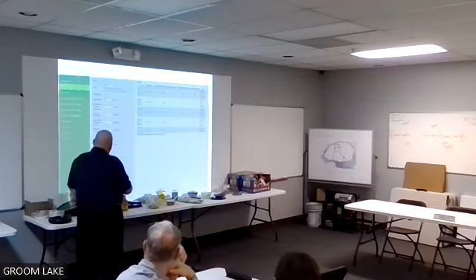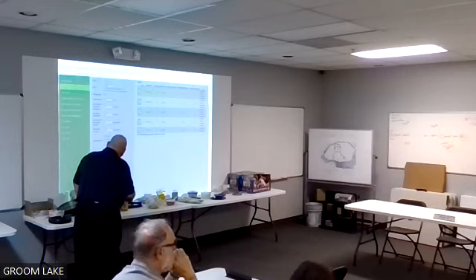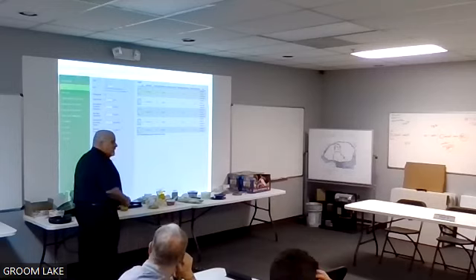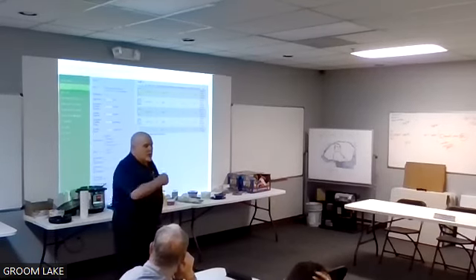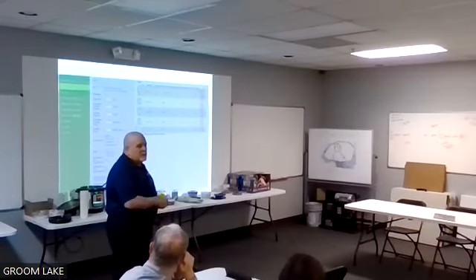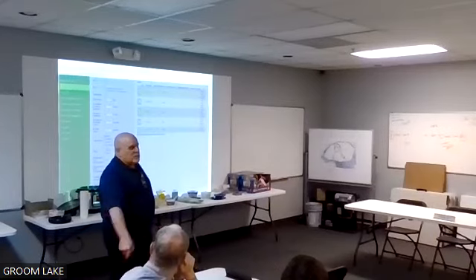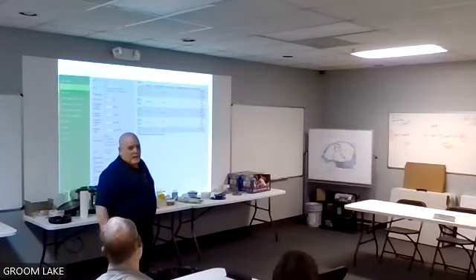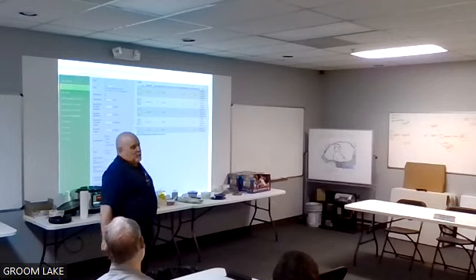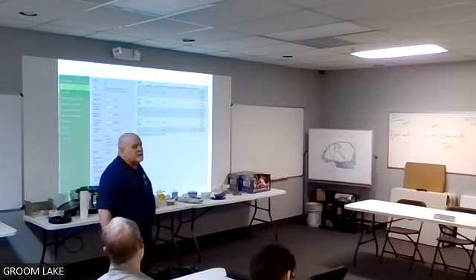And then when you do this down here, if you look, it says right here, specific volume of the fluid, 0.016 cubic foot per pound, and it says calculated system volume 28.3. That tells you right there how much I've expanded my water. But the program will select all this for you. Like I said, you can go to Wessel's, John Wood, everybody's got a sizing program, and they're all this simple to use. So don't worry about pulling up all those equations I just went through. Go to any of those sites and you can just do this yourself.